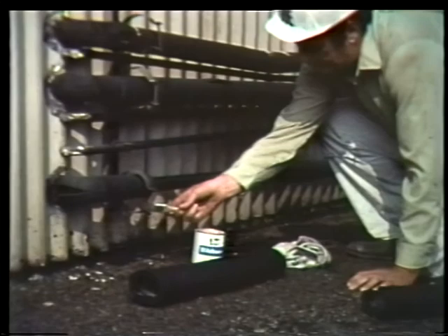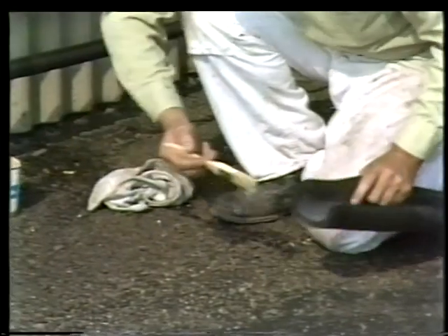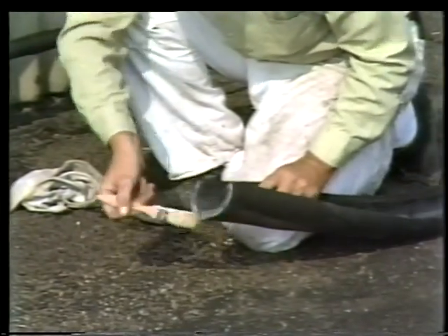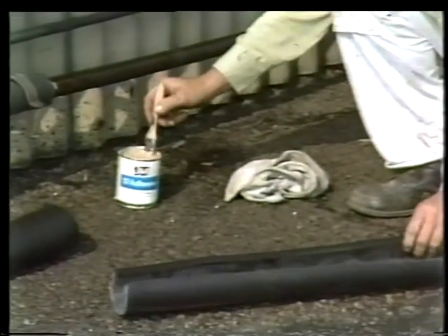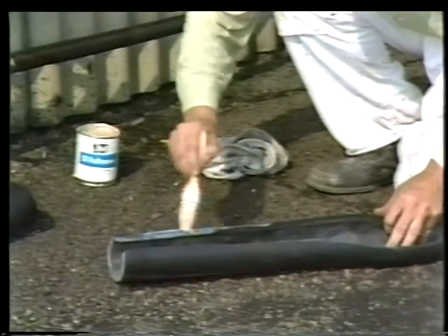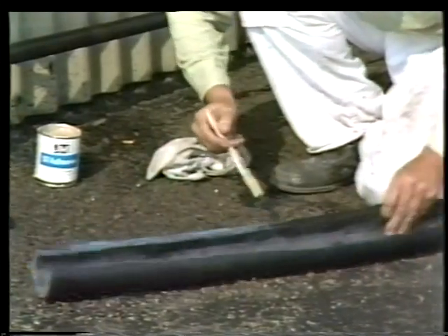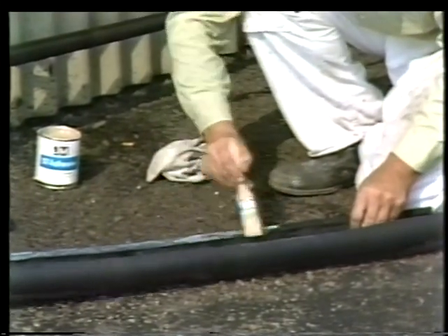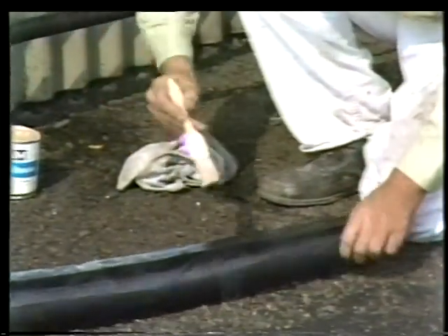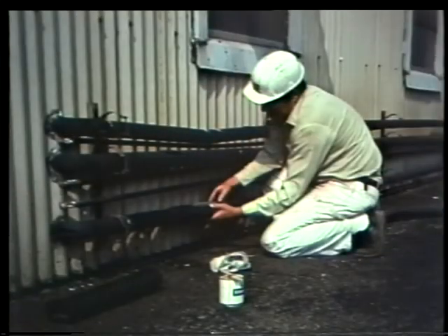First, adhesive is spread on either side of the gap. Then, the ends of the new piece are prepared. The adhesive sets up on contact, holding the insulation together and providing an airtight seal against water vapor in the air. Both sides of the long seam are brushed with the adhesive so they'll stick together as soon as they touch. When all the seams are coated with adhesive, the insulation is mounted on the pipe.